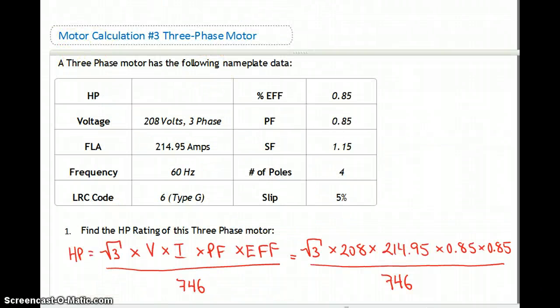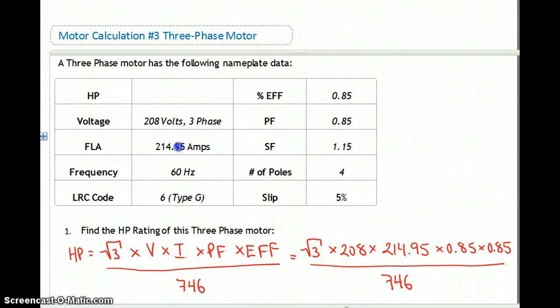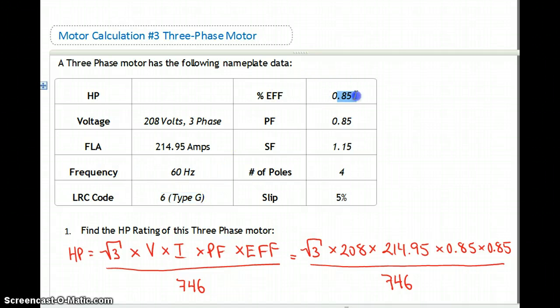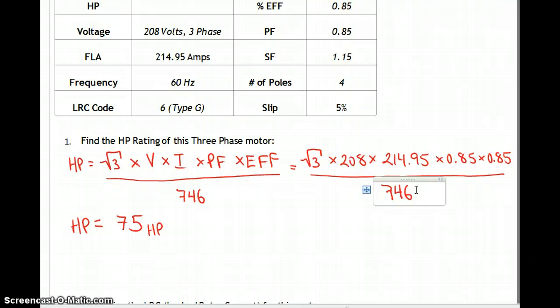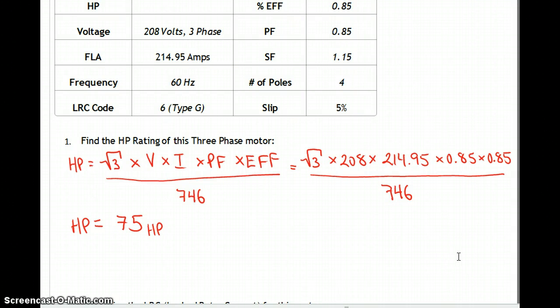Motor calculation number three is a three-phase motor where the horsepower hasn't been given. It runs on 208V 3-phase at 60 hertz, full load current is 214 amps, type G pulling six times FLA, efficiency 0.85, power factor 0.85, service factor 1.15, four poles, slip is 5%. To find horsepower: root 3 times voltage times current gives VA; then VA times power factor times efficiency over 746. This works out to a 75 horsepower motor.